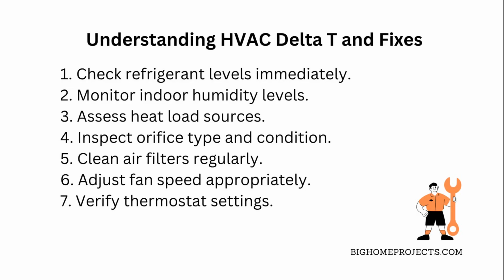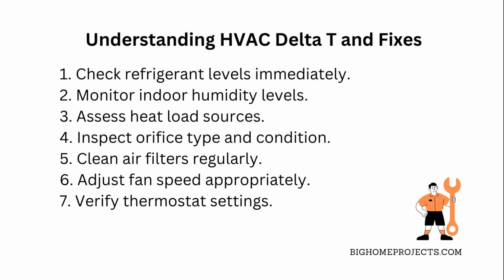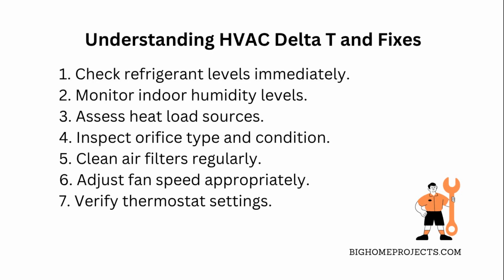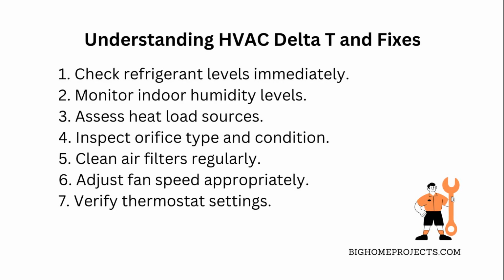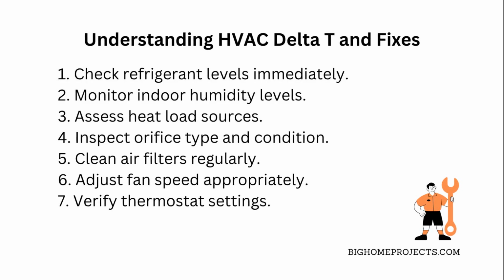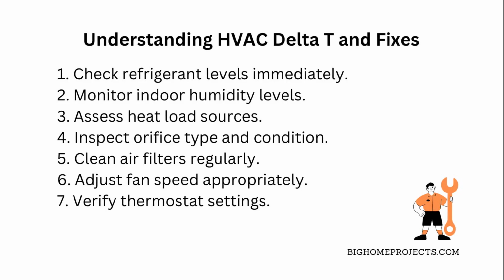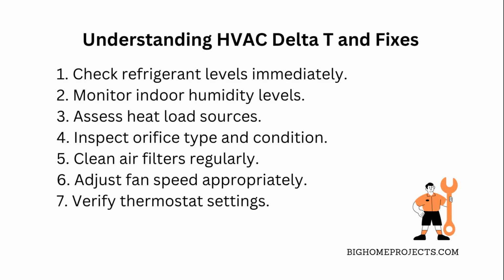off if needed. Next, think about the humidity in your building. If it's super high, it can make your system work overtime and mess with the Delta T. Also, consider if there's a crazy heat load, like too many people or machines pumping out heat, because that can lower Delta T too. Don't forget to inspect the orifice type too. If the orifice is wrong or clogged, the refrigerant flow gets screwed up and lowers efficiency.